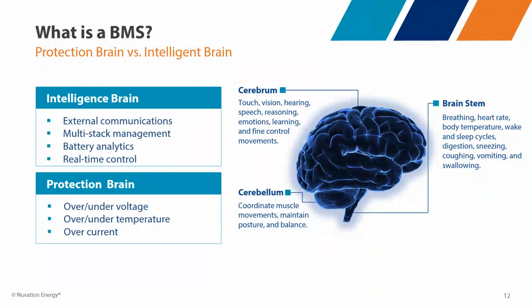Most commonly when people think of a BMS, they think of the protection side of the system, that it's going to detect over or under voltage, over or under temperature, over current situations, and open a contactor. This is maybe 5-10% of what our BMS does. The BMS does a whole lot more than that: managing all your external communications, multi-stack management, doing all your battery analytics, collecting all the data around that, and real-time control of the system.